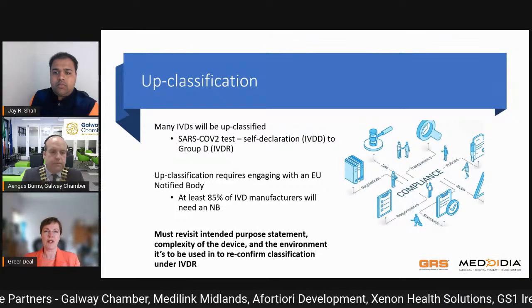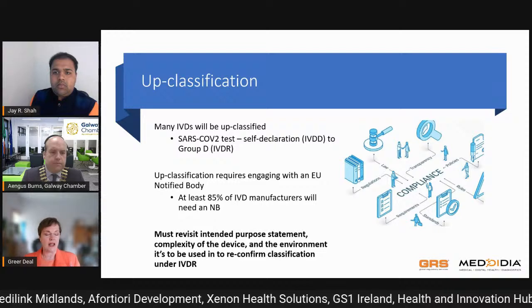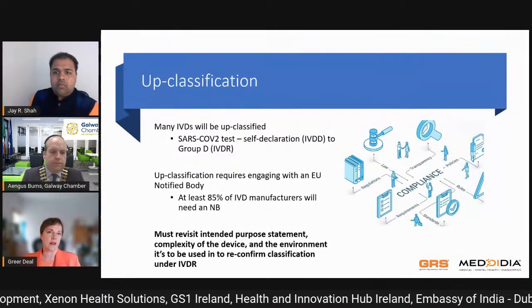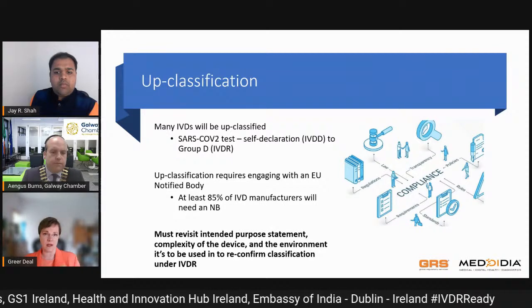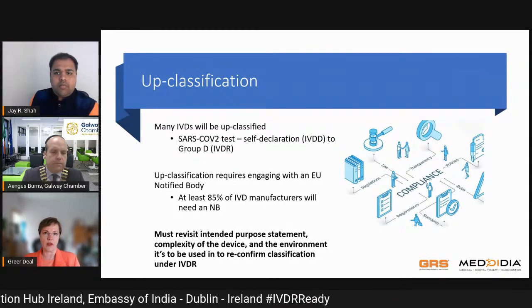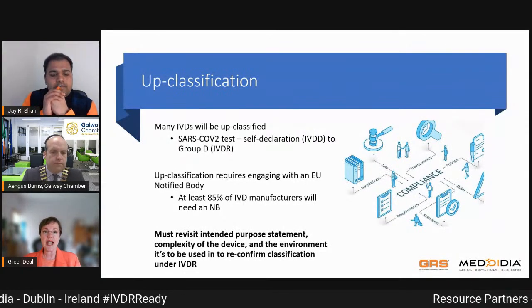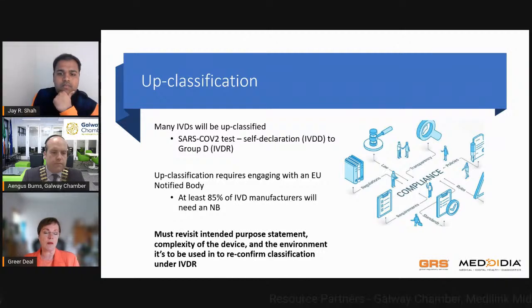And then you need to reconfirm the risk classification of your diagnostic. I would actually recommend that you get someone outside of the company to do that for you, because they will be truly objective and be able to guide you through that process and determine your risk classification. Now, if there are any grey areas, then I would also recommend that you engage with your notified body, if you have one. It may take some time to engage one, or you could go to your competent authority. In Ireland, that's the HPRA, and get their advice and guidance on what they think your risk classification is. When you do that, though, you should be presenting evidence to the authorities to say, this is our reasoning behind why we think our device is this risk classification. Do you agree?